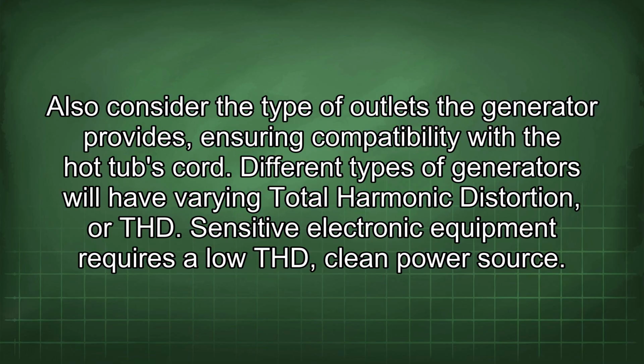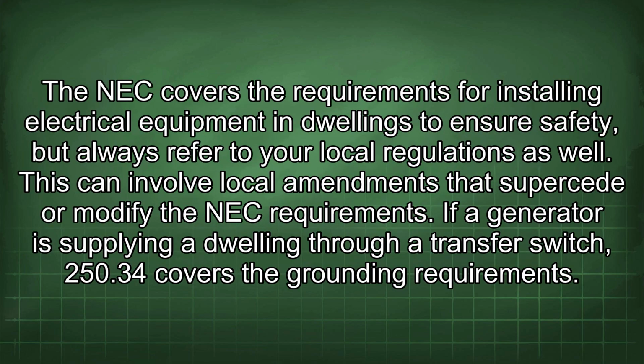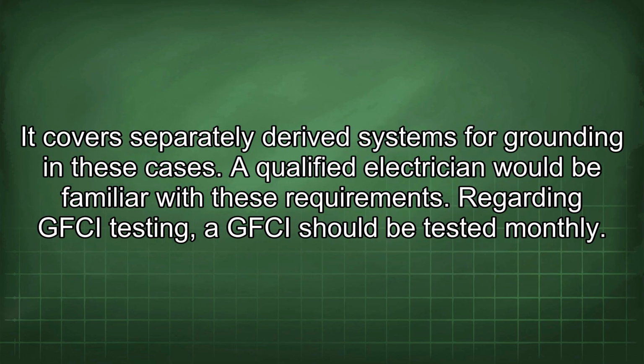Different types of generators will have varying total harmonic distortion, or THD. Sensitive electronic equipment requires a low THD, clean power source. The NEC covers the requirements for installing electrical equipment in dwellings to ensure safety, but always refer to your local regulations as well. This can involve local amendments that supersede or modify the NEC requirements. If a generator is supplying a dwelling through a transfer switch, 250.34 covers the grounding requirements. It covers separately derived systems for grounding in these cases. A qualified electrician would be familiar with these requirements.